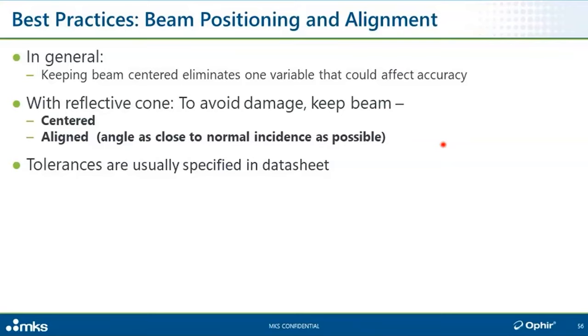When you're using one of those sensors that has a reflective cone, it's more critical to keep the beam properly centered, because there, if the beam's not properly centered, some of the beam might miss the cone and therefore won't get expanded by that divergence angle that the cone creates. And we every now and then get a sensor coming in for repair with burn spots that were clearly caused by a not properly centered beam. You also want to keep the beam aligned. Keep the incidence angle as close to normal incidence as possible. Both of these parameters are usually specified in the data sheets.